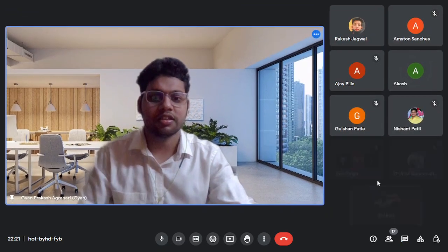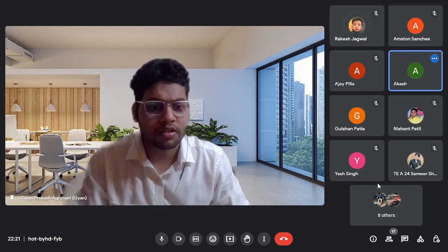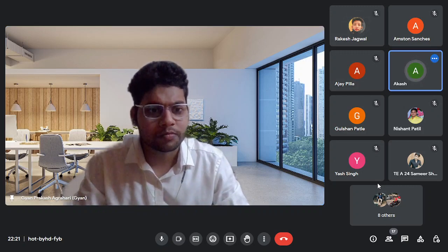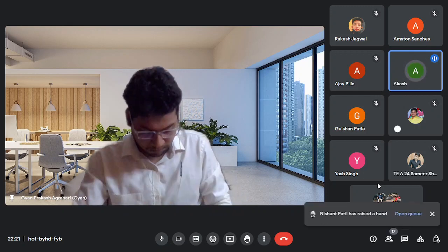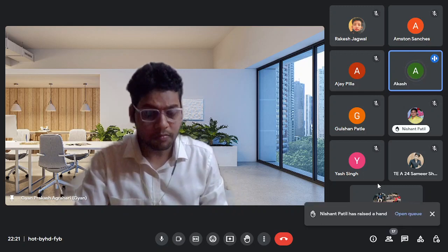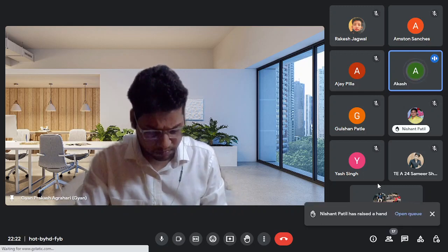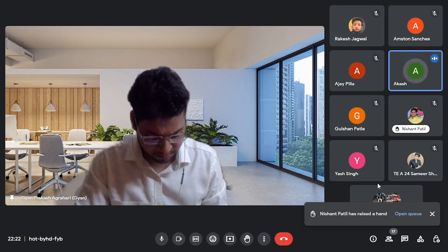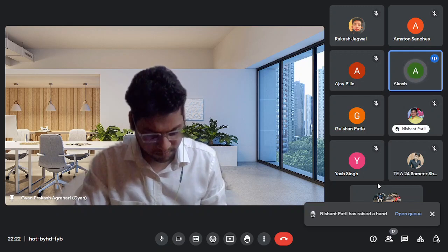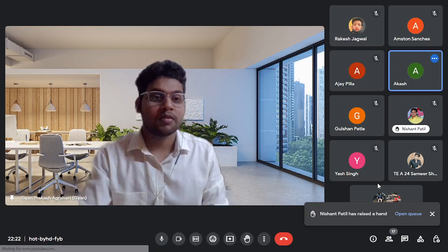Sir, the impeller imparts a centrifugal force to the fluid. Then the fluid possesses kinetic energy, which is velocity. Once the fluid passes to the volute casing, the area of the volute casing increases, thus kinetic energy decreases and pressure energy increases, sir. That is how it creates a discharge pressure using volute casing.